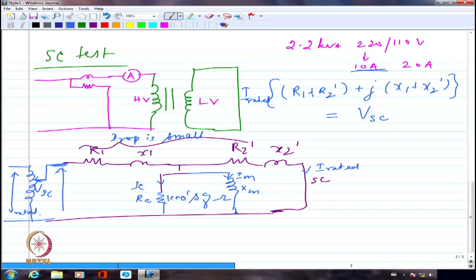So I can't directly apply this here. Let me show this again. This will be connected to a variac like this. The earth point, please note, is the same. So the variac cannot isolate. It cannot isolate between the primary of the transformer under test and the power supply. It is actually the same earth between both of them. So I have to have the power supply connected here. That is where 220 volts is connected.